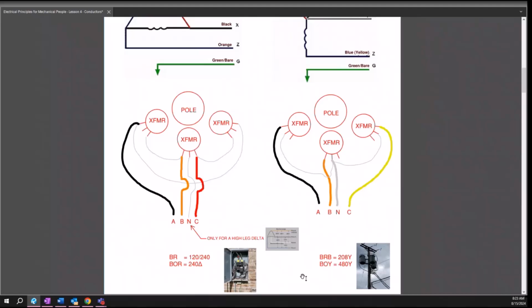90, 95% of the time, utilities will not install a high leg anymore, period. This is from way back when, 50, 60, 70 years ago — these are all legacy installs. However, there's been two instances where I actually was able to get the utility on a new service to install a 240 high leg. I had, we'll just call it 380-something amps worth of 3-phase load — it was a massive industrial facility, nothing but motors across the board.